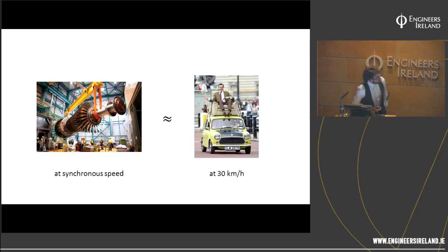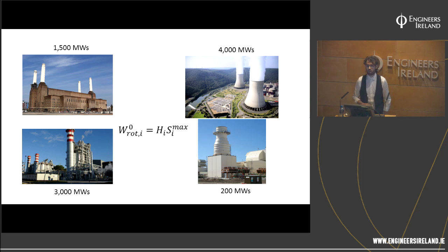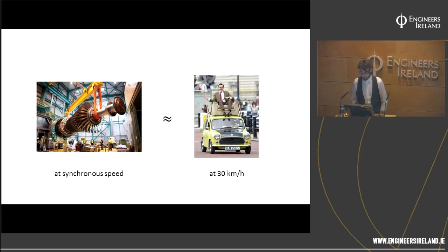To bring it back down to a normal day, this is a brand new turbine from Alstom. When that's rotating at synchronous speed, let's assume we have that 3,000 megawatt seconds, that stored energy is roughly Mr. Bean on his Mini moving at 30 kilometers an hour, including the mop, Mr. Bean and the chair. So that kind of gives you a feel for how much energy we're talking about.